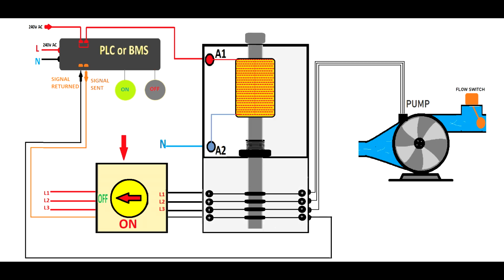When you enable the contactor, you will see that the programmable logic control sends a signal, but the signal will stop at the isolating switch. So the signal is not going. That tells the person monitoring the system that the circuit is interrupted. So the pump is not running. And then he can send an electrician to say, okay, look, the signal is interrupted.